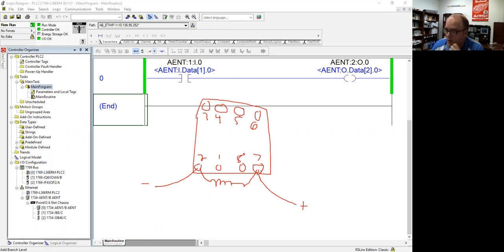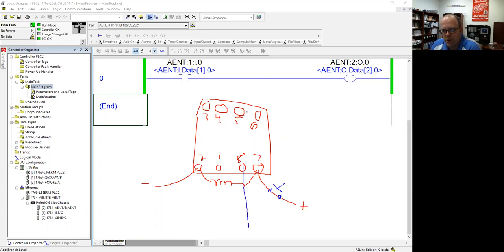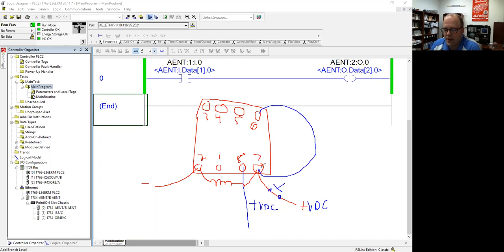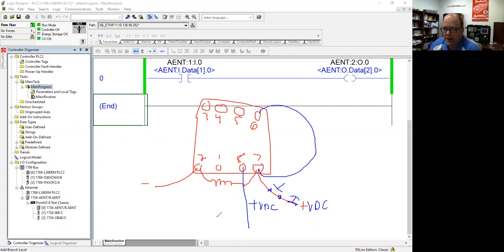So if I have a push button here, when I press it, power goes to the coil, which closes the contacts and turns the motor on. In motor control, what we've learned to do is take one side of the relay tied into your plus VDC, and through the normally open terminal run a tail back — because once this is on, it keeps the power on until something disconnects it. We usually put a normally closed stop button in there.